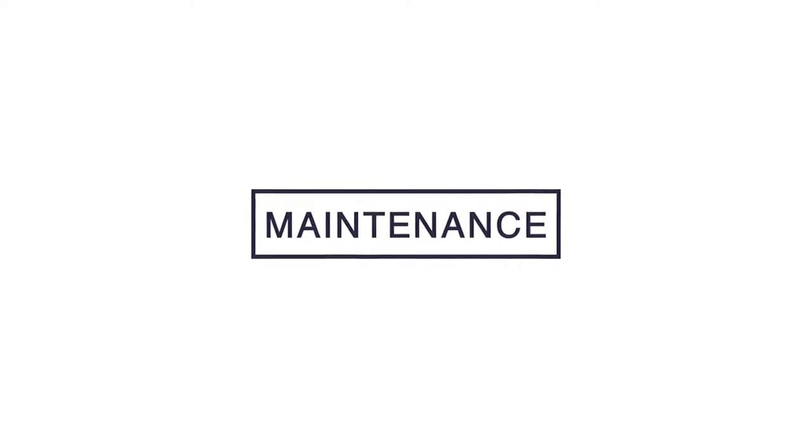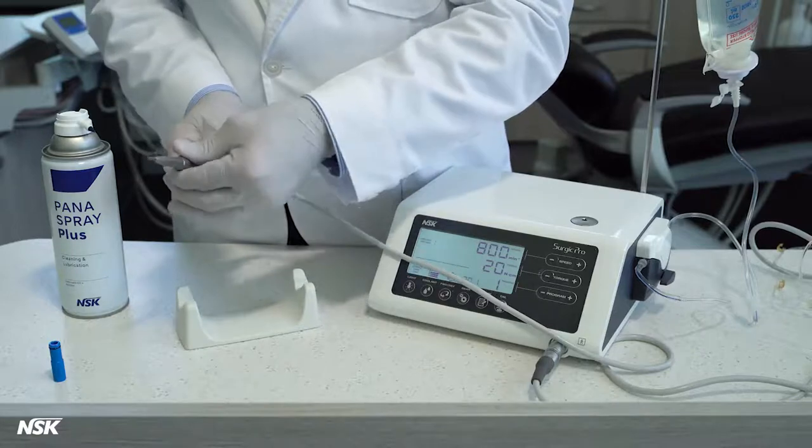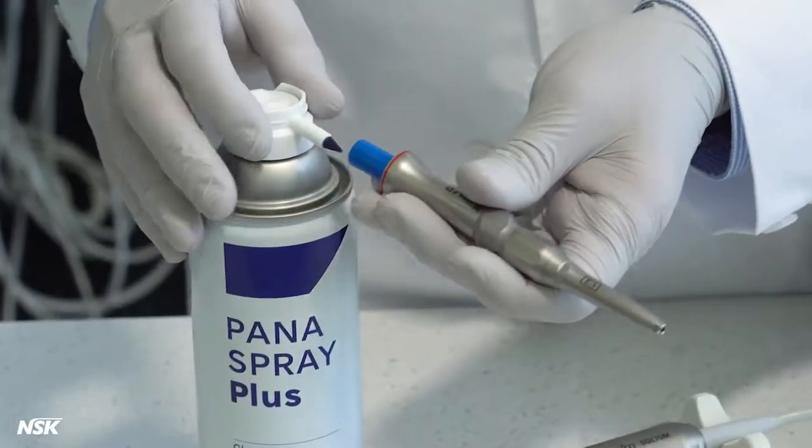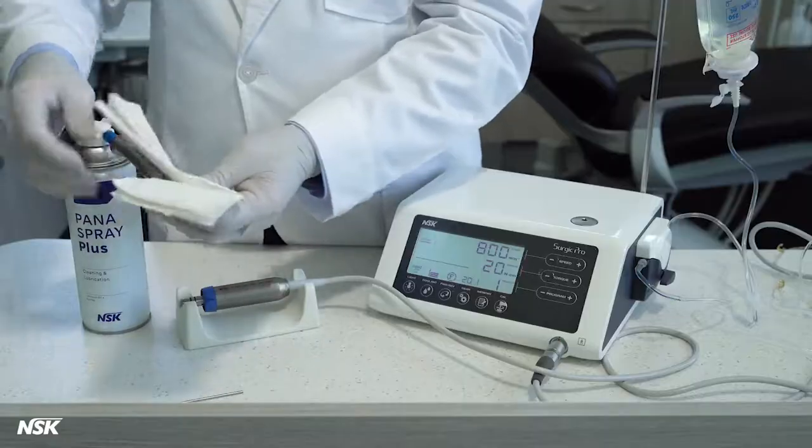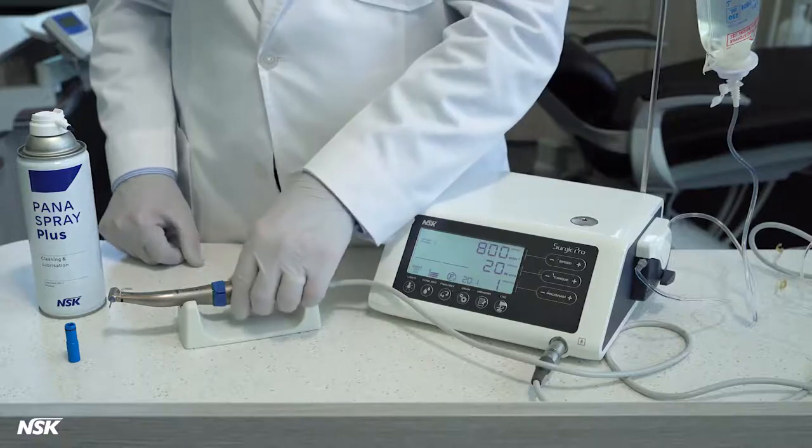Care and maintenance: After each operation, it's important to immediately clean and lubricate the attachment. During procedures, blood and other oral fluids are sucked into the internal gears. These fluids can dry in less than a minute and cause damage to the attachment. Here's how we do it.